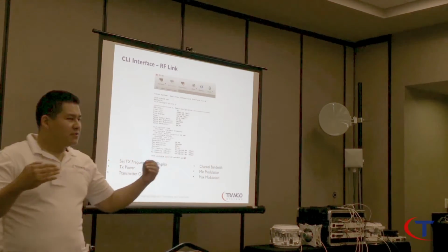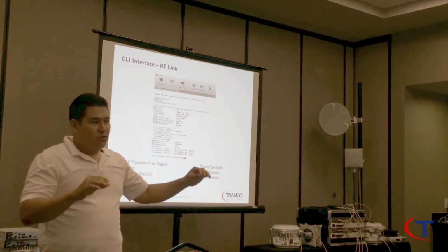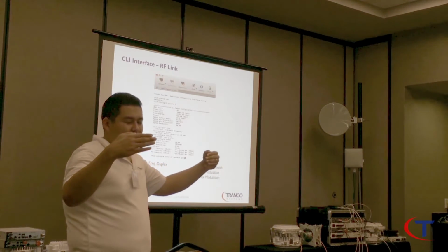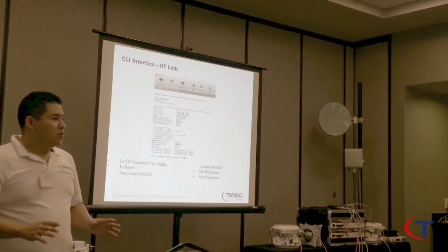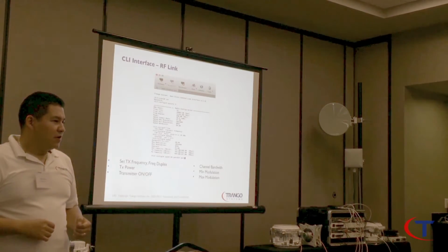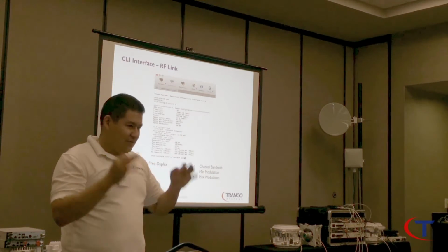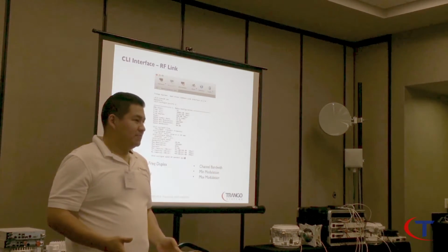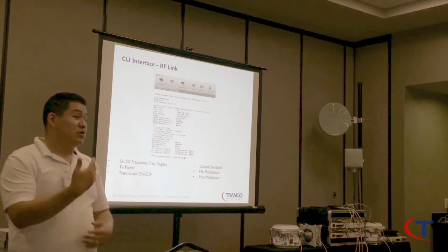If my RSSIs are not symmetrical, what's going to happen? If they're not symmetrical, but one is, for example, -50, -60, check the transmit power first. One may be 10 dBs higher than the other. If the RSSI is symmetrically bad, it's 100% alignment, no way around it. You have to go up, check the alignment. I cannot tell you which side, one or the other.